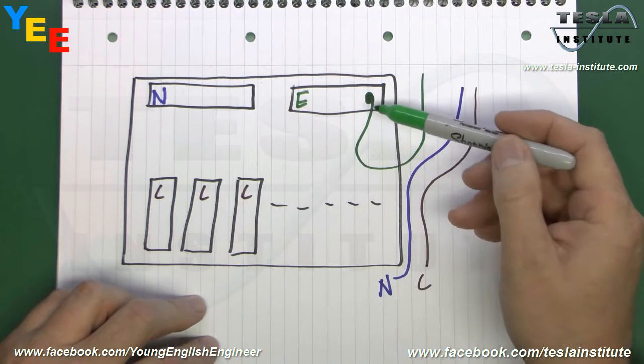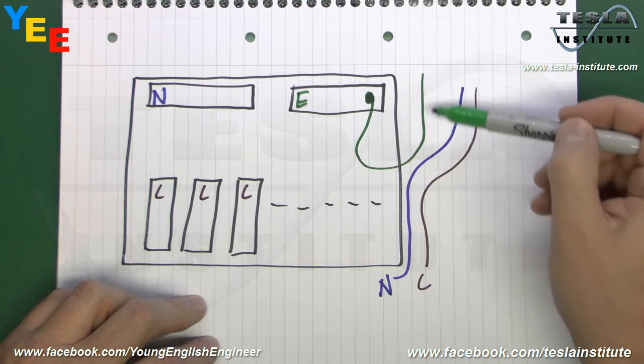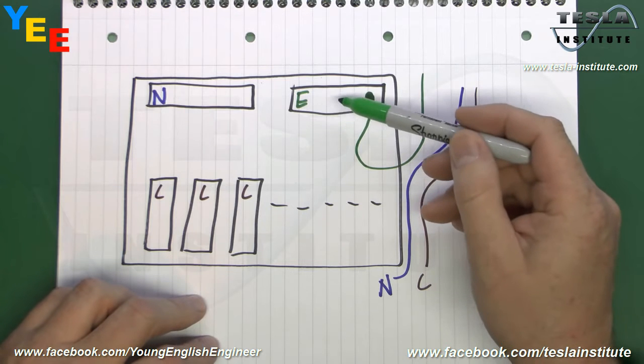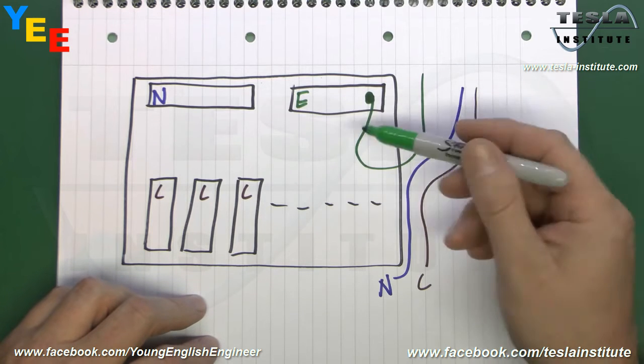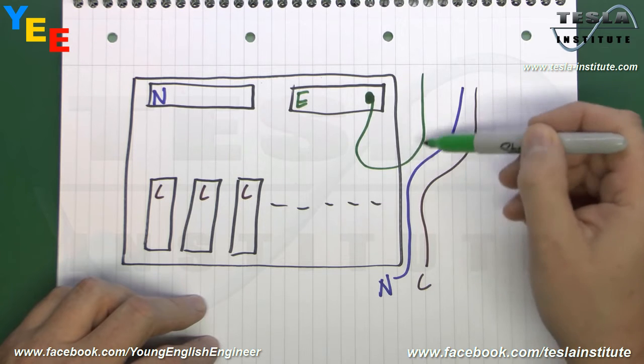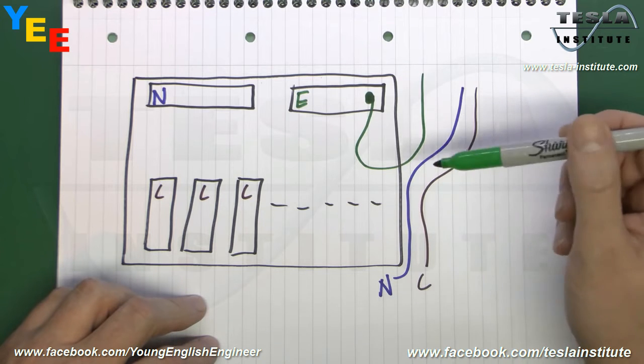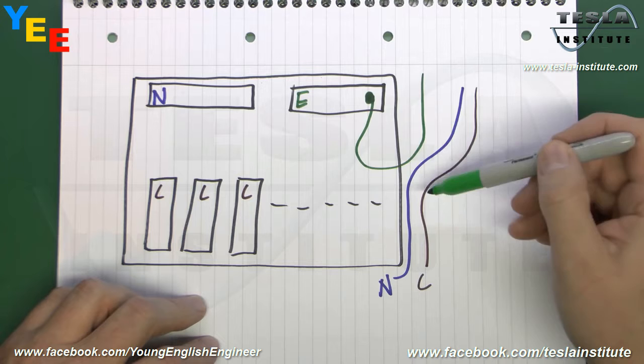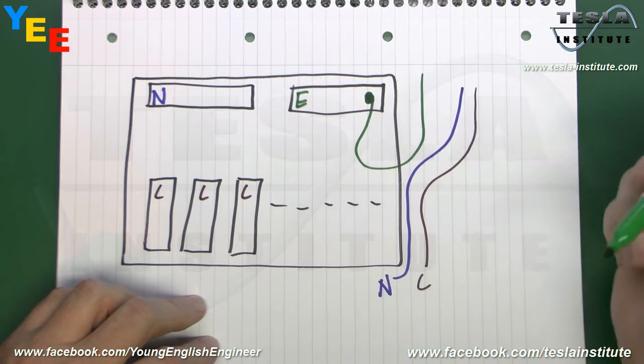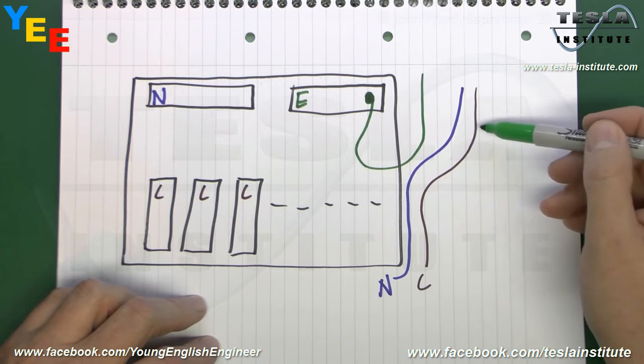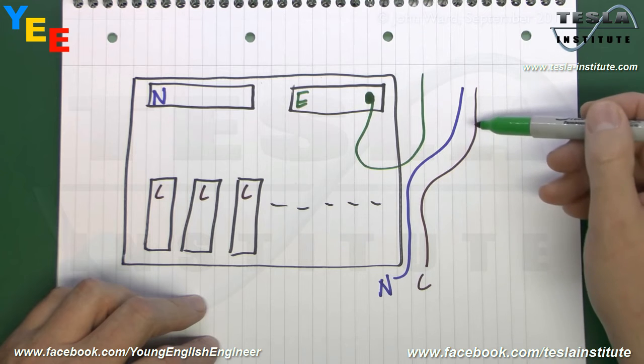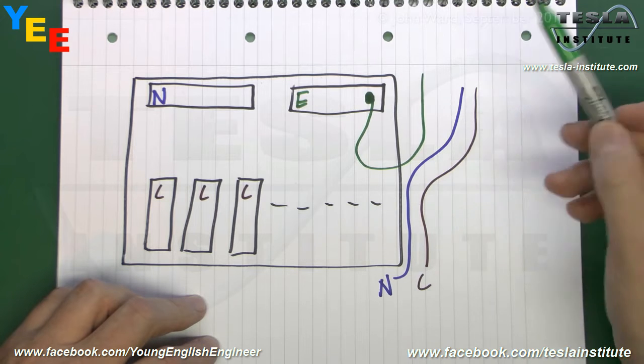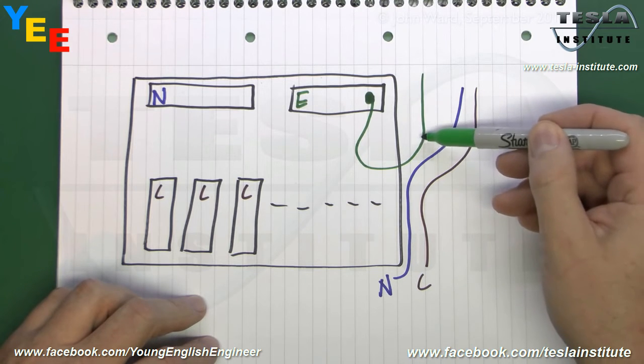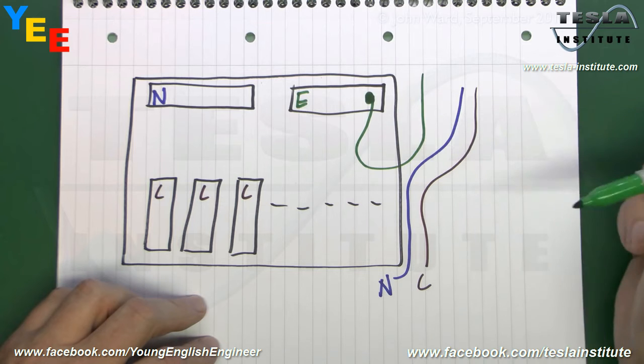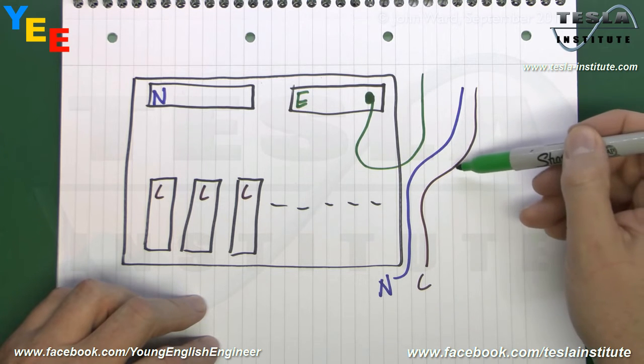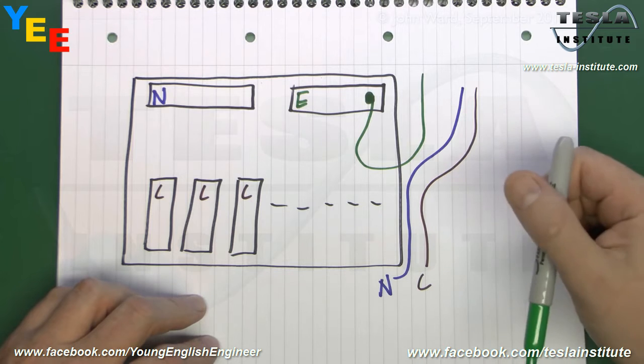And this is important because it means that the protective conductor for the circuit is now connected to the earthing for the installation. So you're not only testing between the actual wire itself and the other conductors, you're also testing between these conductors and the installation earth itself. This is useful because if you had, say, a fault on one of these conductors, say it was an underground cable and it became damaged, it may not have a fault between the actual wire and, say, the line conductor, but there could well be a fault between the conductor and, say, the ground or the earth that it's buried in itself.